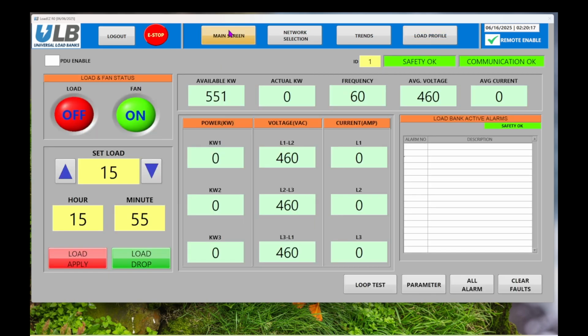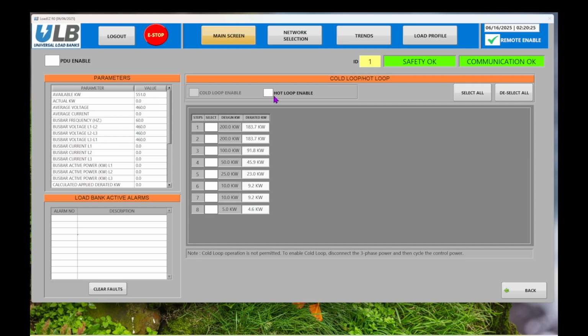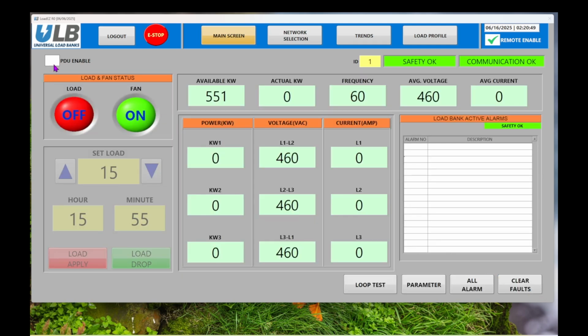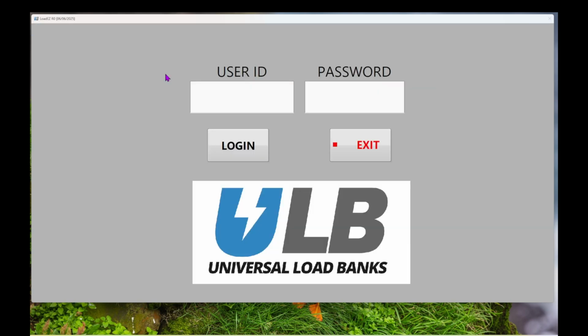Back on the main screen, click Loop Test for hot or cold loop testing. Cold loop testing should only be done when no power is connected to the bus bar. To perform it, disconnect power to the bus bar, connect only external control power, turn on the load bank, and proceed. For a hot loop test, connect three-phase power to the bus bar, then turn on the required load steps and apply or drop the load. When PDU Enable is selected, LoadEZ will allow you to perform a PDU test. To exit the application, first press Log Out, then press Exit to close the LoadEZ software completely.